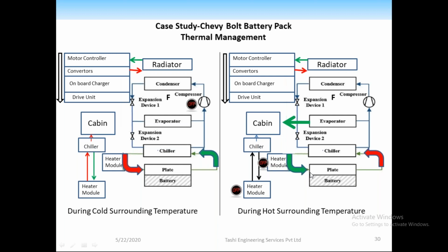I'll let the cold water-ethylene glycol through this plate. It will become hot by taking battery heat, then go into the chiller. This chiller is basically a heat exchanger between the refrigerant and the water-based ethylene glycol solution. I reject the heat to the chiller and the cycle continues so that my battery pack is maintained at 25 degrees Celsius.